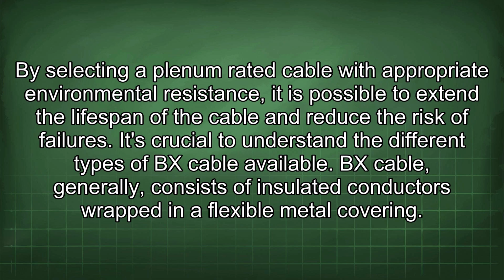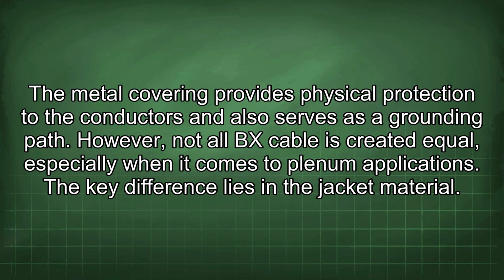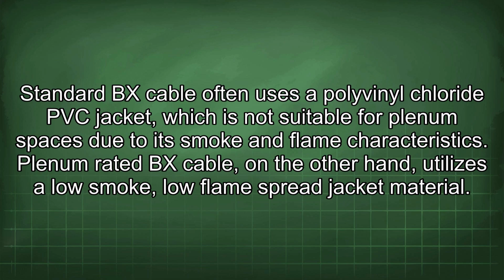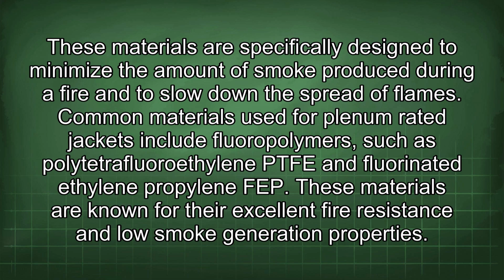It's crucial to understand the different types of BX cable available. BX cable generally consists of insulated conductors wrapped in a flexible metal covering. The metal covering provides physical protection to the conductors and also serves as a grounding path. However, not all BX cable is created equal, especially when it comes to plenum applications. The key difference lies in the jacket material. Standard BX cable often uses a polyvinyl chloride (PVC) jacket, which is not suitable for plenum spaces due to its smoke and flame characteristics. Plenum-rated BX cable, on the other hand, utilizes a low-smoke, low-flame spread jacket material. These materials are specifically designed to minimize the amount of smoke produced during a fire and to slow down the spread of flames.